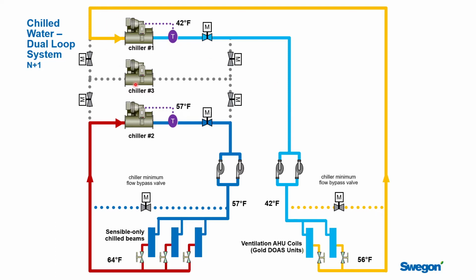and we call it kind of an N+1, but let's look up here. We have 3 chillers all set up in here. They're all valves so we can change the flow. And right now, this is just a different layout of what we saw on the last screen, right? We have one chiller that's servicing the chilled beams. It's making 57-degree water. It's enjoying a very small lift, and so you're going to get a very high COP. And that system is running around in here, doing its job, and servicing the chill beam loop.